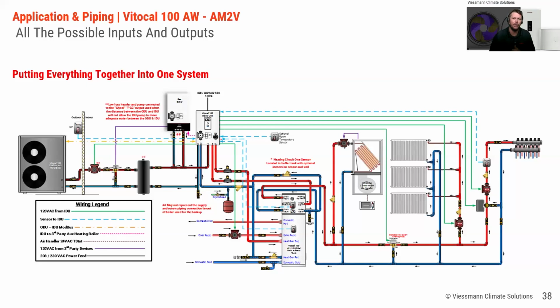Make sure you follow all electrical codes and things like that. One other thing to point out is the indoor unit is a 4-wire, so it's line, neutral, ground, so you need a neutral. The outdoor unit doesn't need a neutral, so it's just line and ground. Correct. Those were the 3 questions we had open. Great questions, so I'm glad we got to use that.